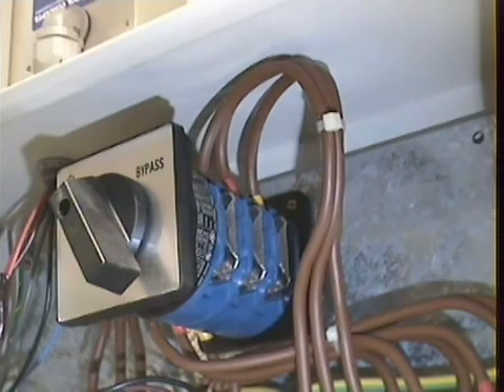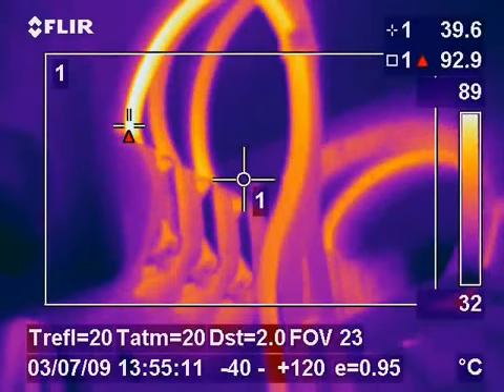In this image we are looking at a UPS bypass switch feeding the comms room of a large commercial building occupied by an IT company. The control gear looked perfect to the naked eye, but under inspection with the thermal imaging camera a critical fault was found which otherwise would have caused a catastrophic failure or even a fire in the comms room, which would have cost huge sums of money and massive downtime would have been incurred. After identifying the fault, it was able to be rectified within 24 hours and no loss of production was incurred by the company.